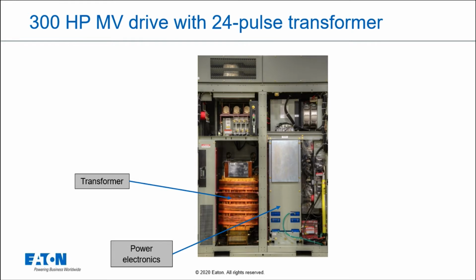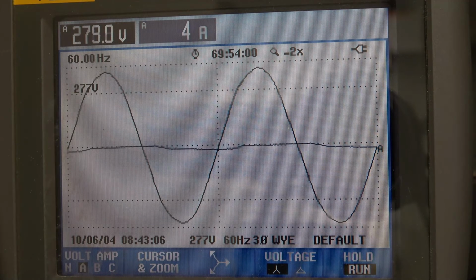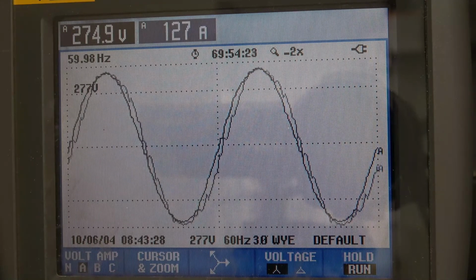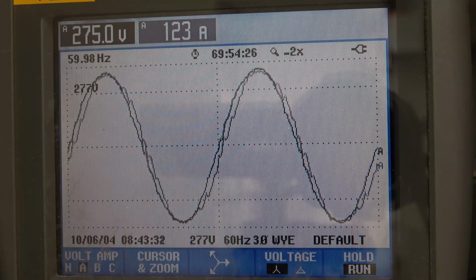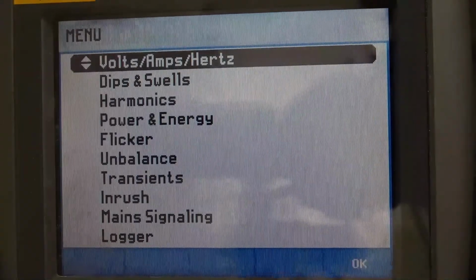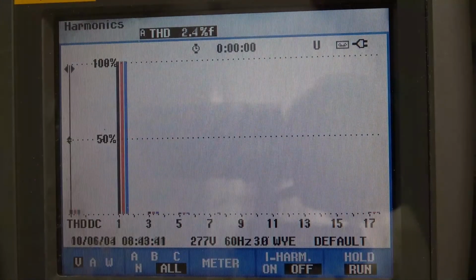I'm going to switch over to the camera, and we'll take a look at 24 pulse phase cancellation. So what I'll do is, this is my voltage on the system, and I'll start up all 4 variable frequency drives with the phase shifting transformers in front of them to show at the 480 volt level here what that would look like, and we'll end up with 24 pulse cancellation. So you can see the current looks very similar to the voltage. It has a very low distortion level. In fact, the harmonics that we expect are going to be way out there, again, the 23rd, 25th.